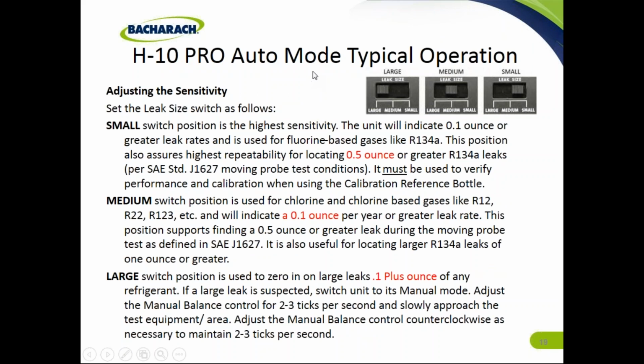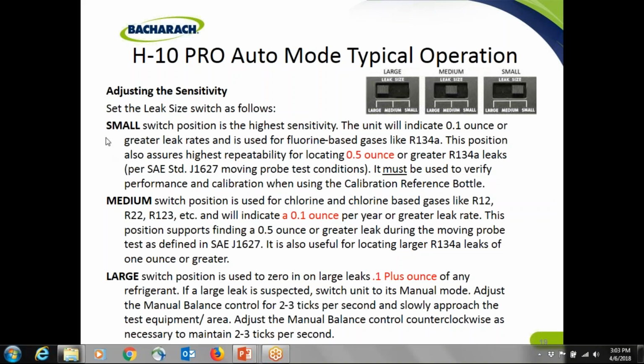The H10 Pro auto mode, typical operation. Here you have the leak size switch. So you have a large, a medium, and a small. The small switch position is the highest sensitivity. The unit will indicate 0.1 ounce or greater leak rates and is used for fluorine-based gases like R134A.